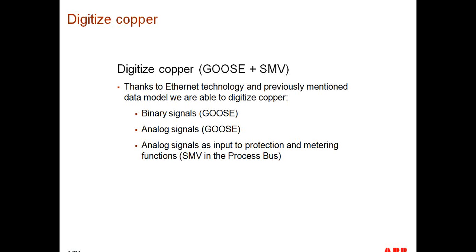61850 is the part where we are replacing what's done today via copper wires with digital Ethernet-based messages. What we're referring to in this webinar as digitizing copper is accomplished by GOOSE messages or sampled measured values. With GOOSE messages, you can share binary signals in a high-speed fashion, or analog signals in a high-speed fashion. This analog exchange is asynchronous, so it cannot really be used for protection functions, but the protocol allows you to send information other than digital information, let's put it that way. And then we have sampled measured values in the process bus, which is a synchronous exchange of analog currents and voltages for the execution of protection or metering algorithms at the relay.